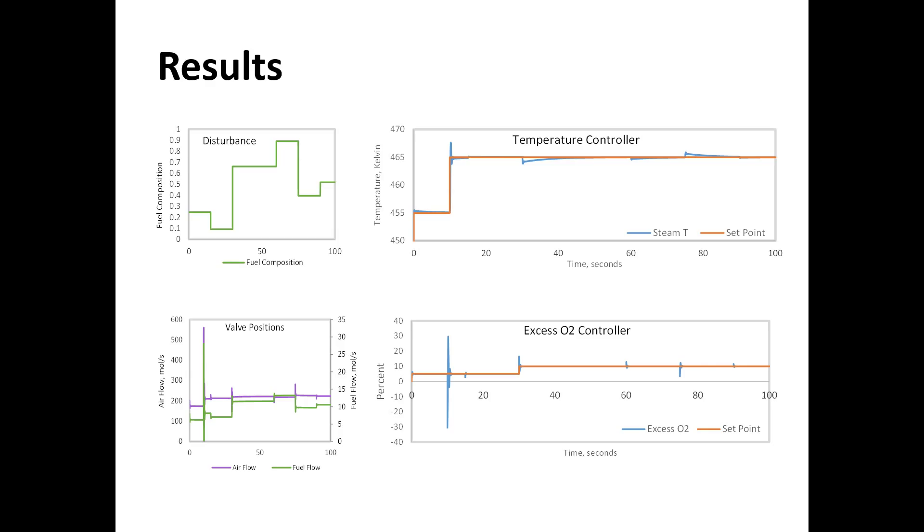We had a set point change in each the amount of excess O2 and the temperature controller, but we tuned our controllers to favor disturbance rejection over set point tracking because the set points won't change very often but the disturbances happen all the time.